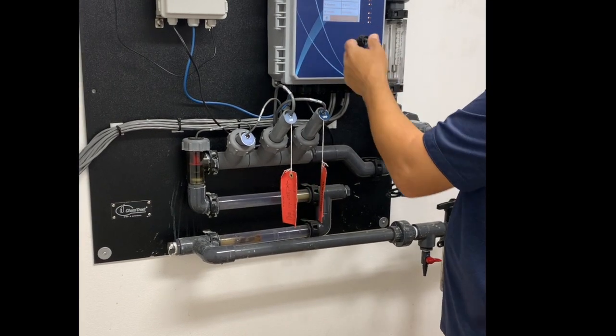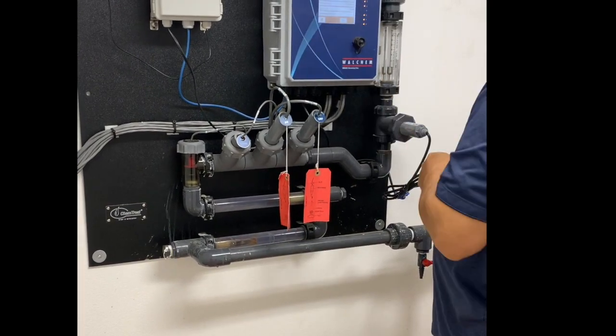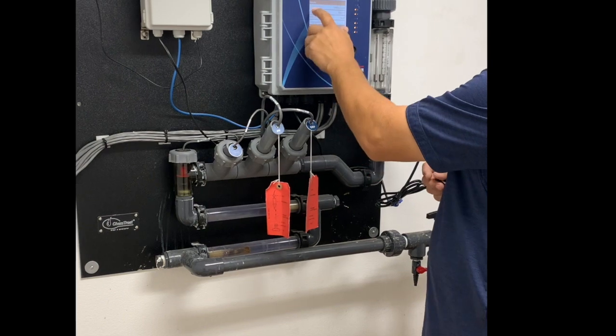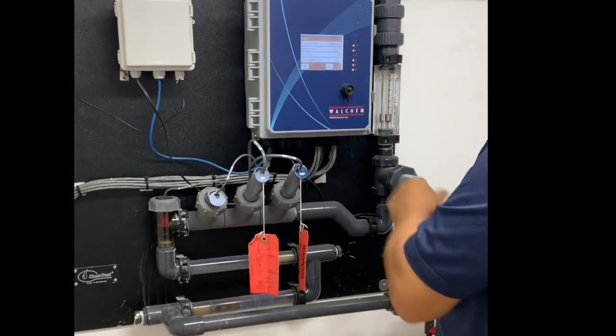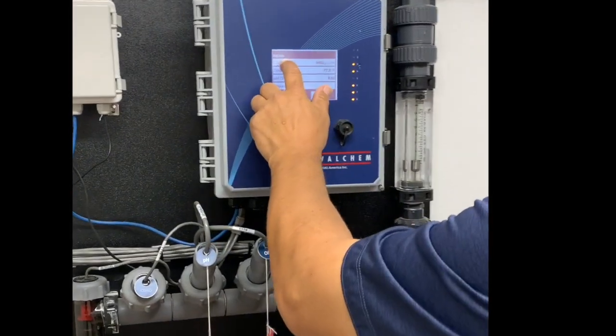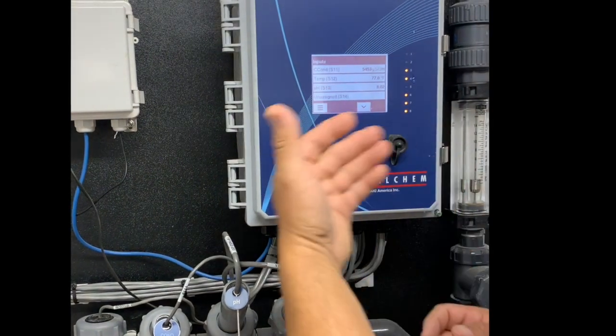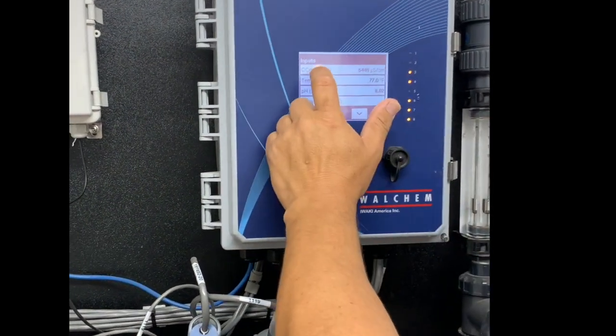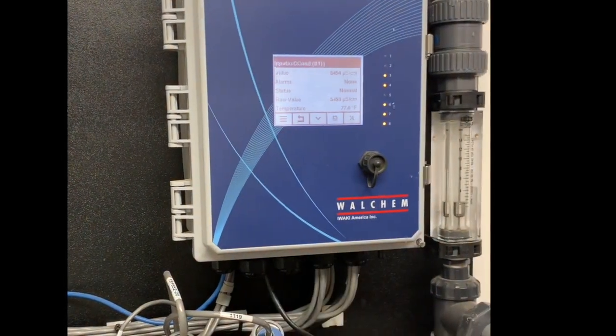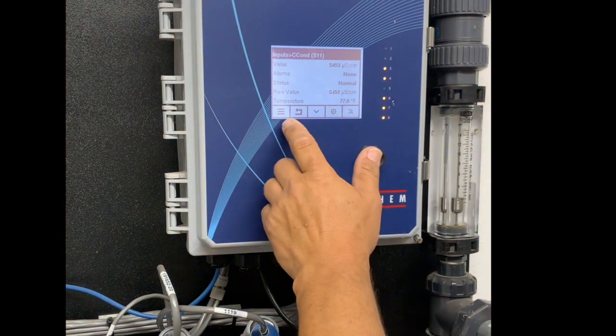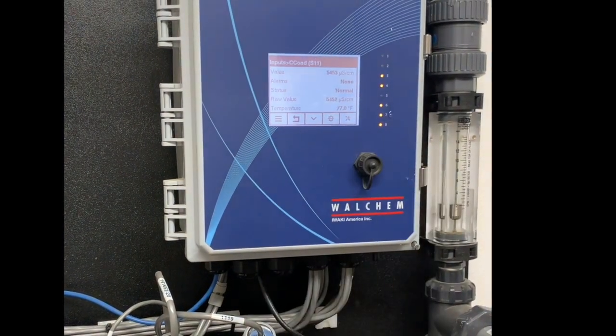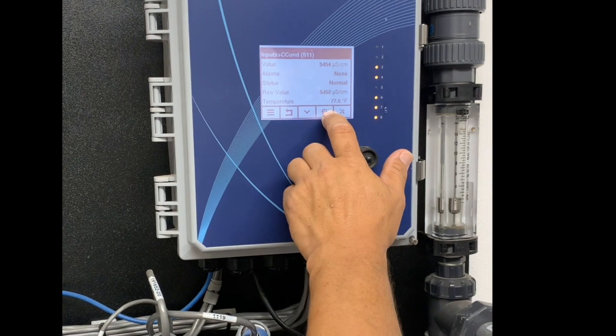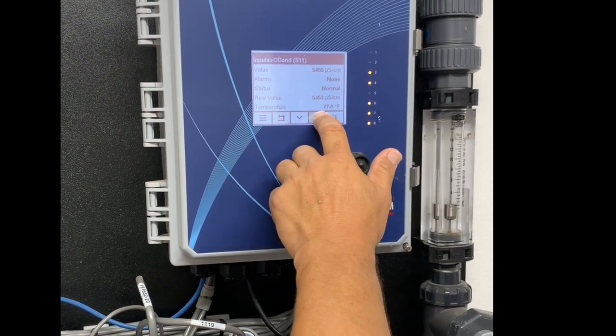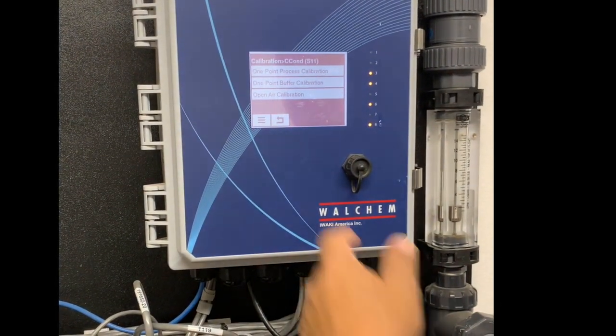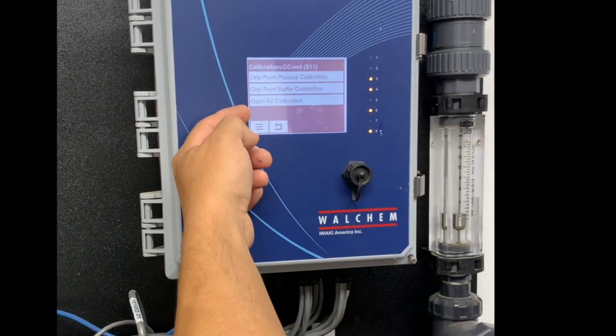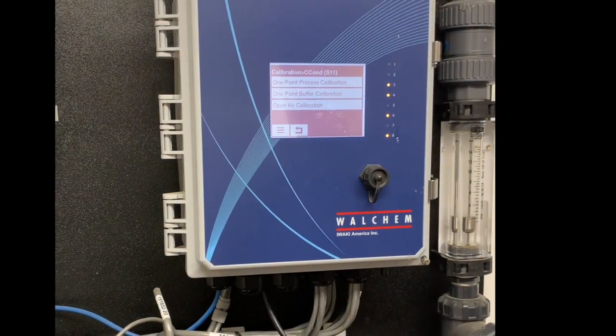But the most common way is we'll go into our inputs, because it's an actual probe. We'll go into our conductivity probe, contacting conductivity in this case. If it was a pH or if it was ORP, you would do that as well. We're going to hit conductivity. Now you have these different icons here at the bottom. The icon you're looking for is the calibration icon. You'll hit that, and you're going to see that you have different options in calibrating.